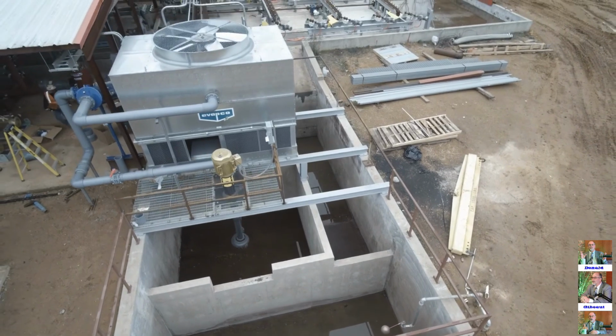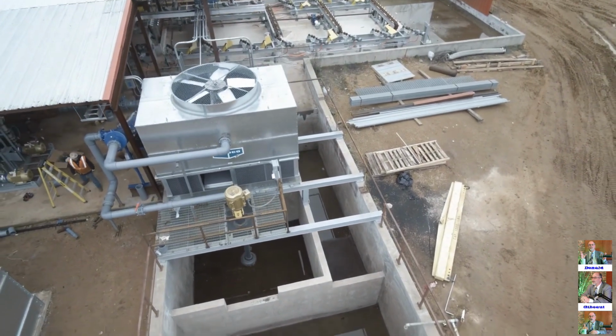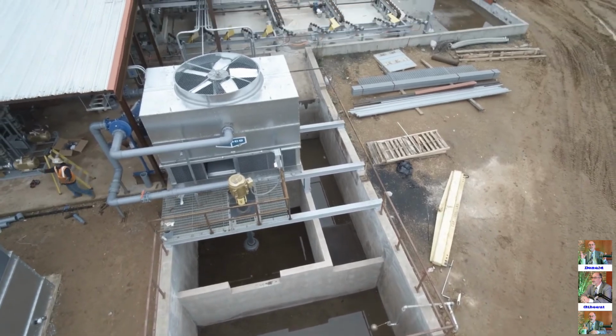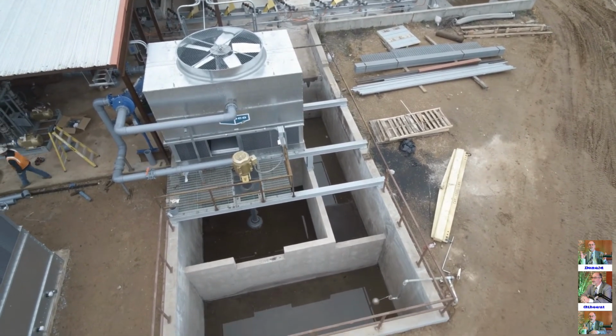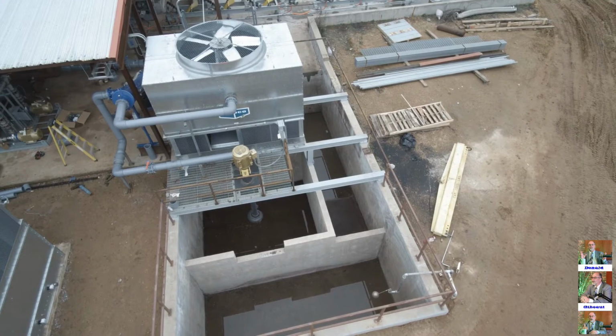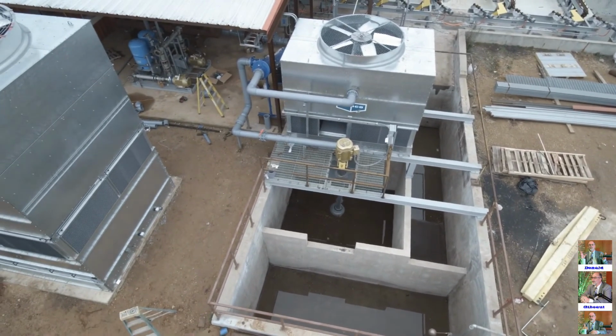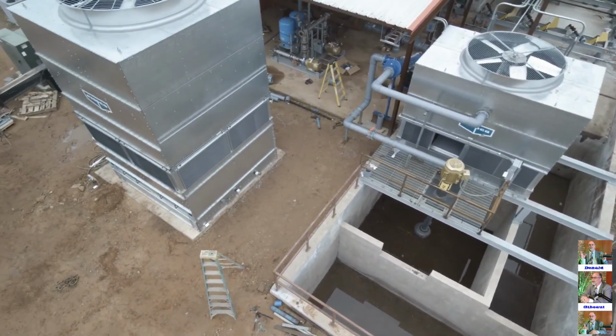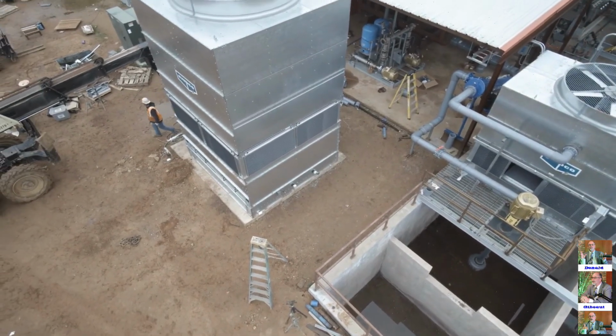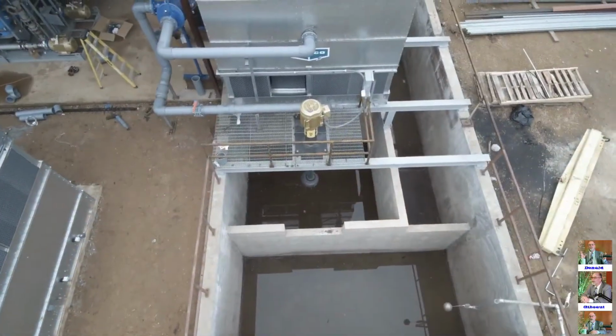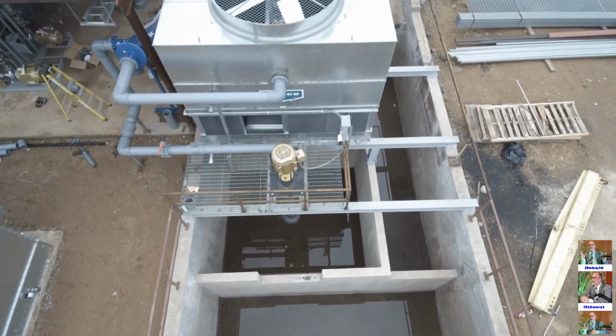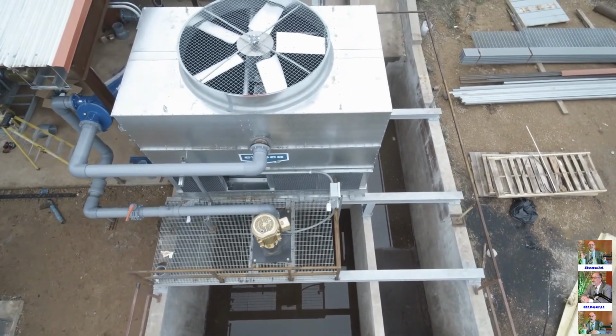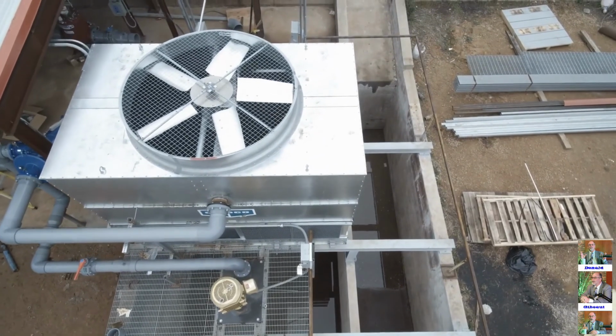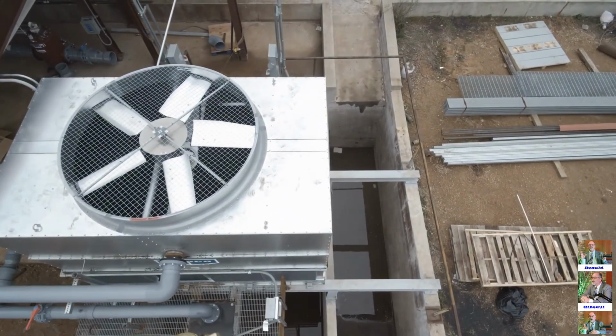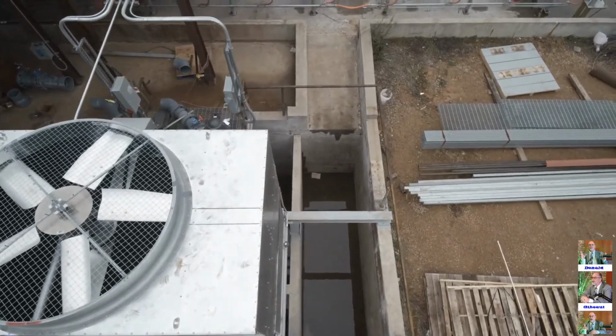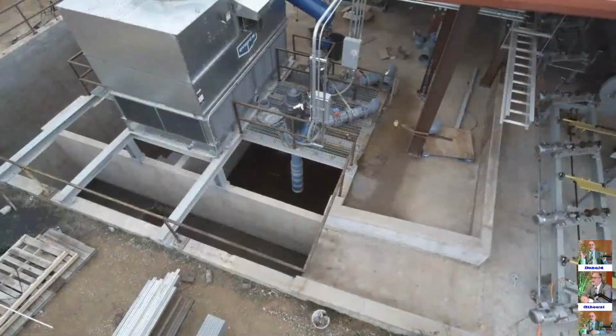Now here's the drone footage I was telling you about where you can see the weir walls. The quench comes down that trough into that first cavity where all the scale is put in, and it spills over into the second cavity there and then goes over into the hot well, which has the pump for the centrifugal separator. You can see the pump here and the weir in that concrete wall. Again, this was on the initial startup. This is footage that we were targeting because it just wasn't available.